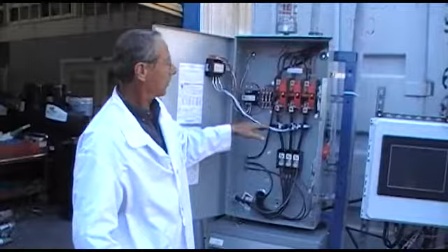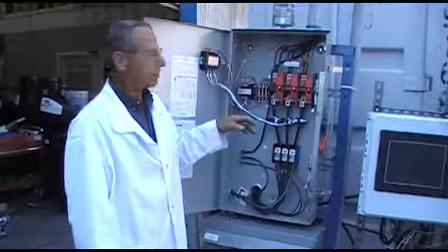We have the current transformers, currently disconnected and turned off, that measure the current on the 480 volt leg. We have our power light. We have isolated the voltage that feeds the meter and the light, so we get a true representation of only the current being used by all the equipment in the reactor.